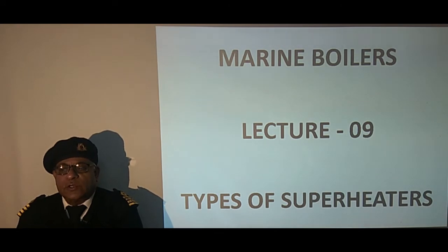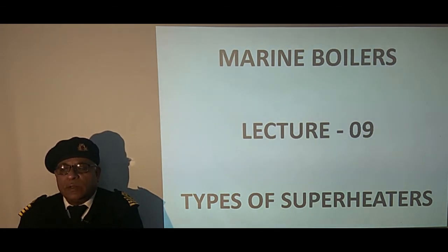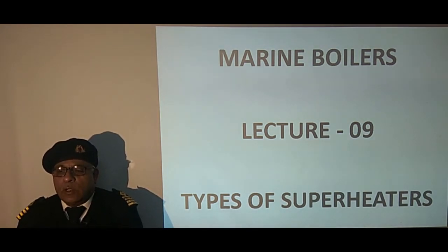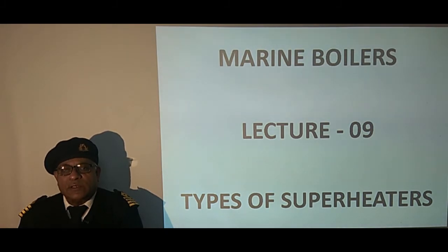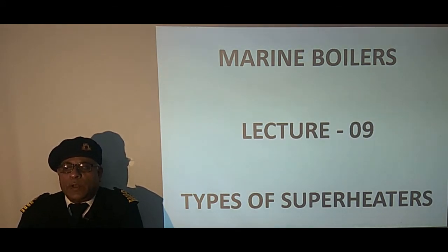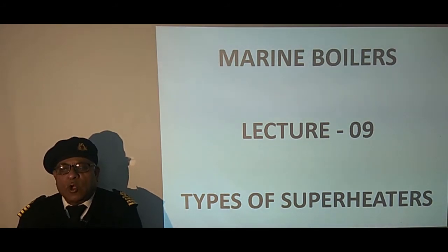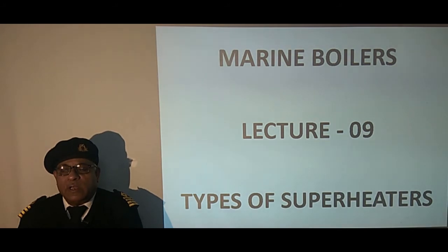Superheaters are used to drive steam turbines which, if driven by saturated steam, would be damaged as their blades get eroded due to water droplets in wet steam. This tutorial does not discuss superheaters used on earlier smoke tube boilers, as low pressure smoke tube boilers are not used for driving steam turbines nowadays. Superheaters are the most delicate component of water tube boilers because the specific heat of steam is less than 50% that of water, which makes them very susceptible to overheating and subsequent damage.